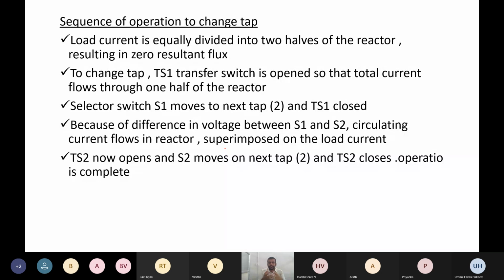So here, if you are interested to change the tap position from one position to another position, at that time the TS1 transfer switch is opened so that the total current flows through one half of the reactor. So the transfer switch is opened so that the total current flows through one half of the reactor. So some amount of current will be flowing into the reactor normally. So if you are going to change the position, at that time you have to open the TS1 switch. You have to open the transfer switch 1. So at that time the current that is flowing through the reactor should be one half of the current that is flowing from the TS1.